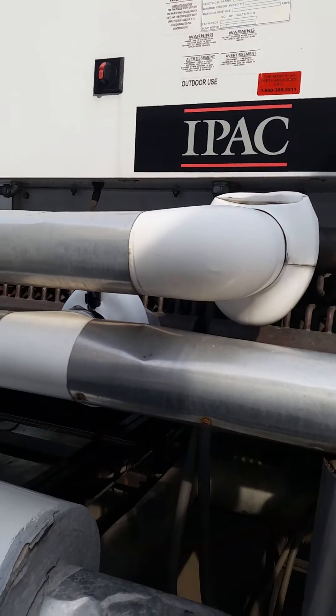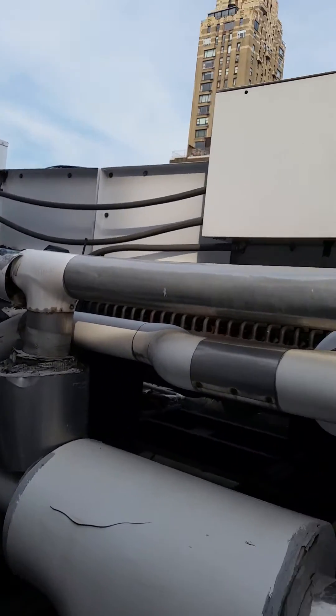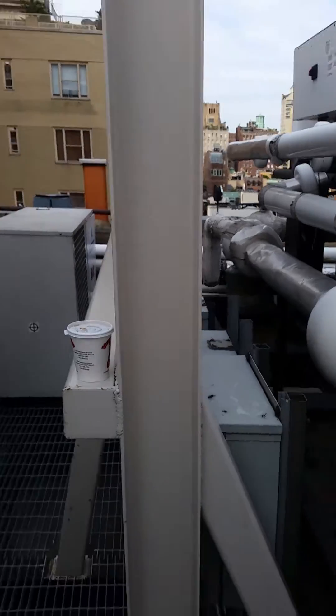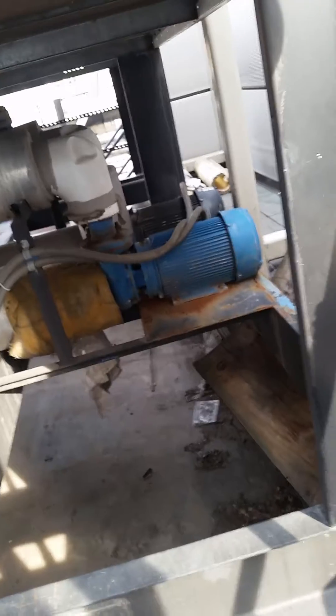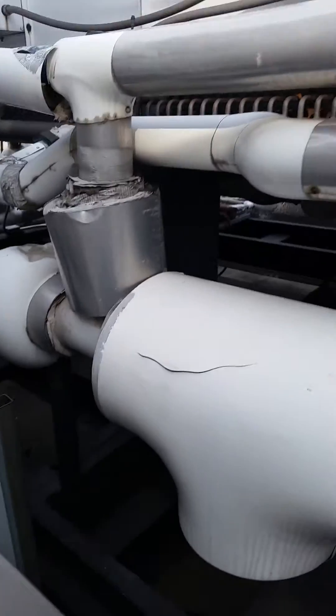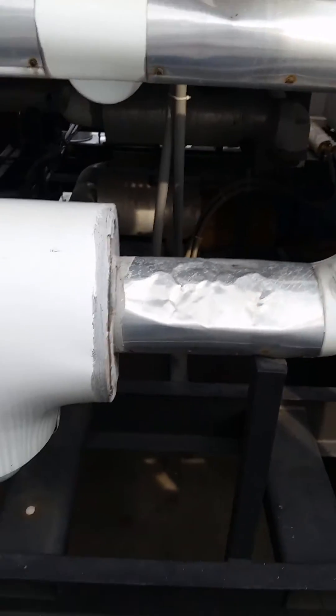This building has water source units — they're not heat pumps. This building has hot water radiators for heat. That's a dry cooler. It's your pumps — your main pump runs the system and you've got a backup. I don't see anywhere where you'd be adding your glycol, though. I've looked. You have some expansion tanks and stuff, so that's about it.